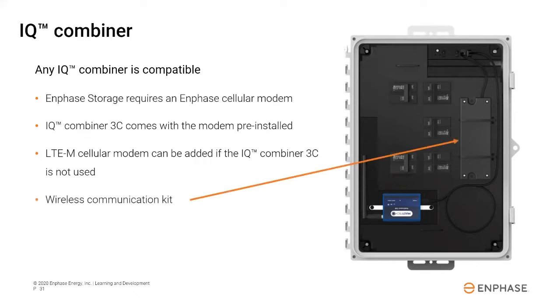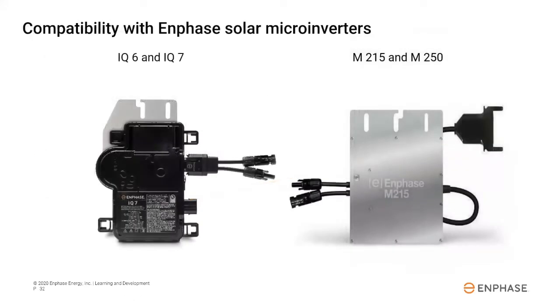And here we have the communication kit. So this must also be installed in the combiner. It's always a separate item. And there's a spot right on the dead front of the combiner box to attach it, and it plugs into the Envoy with a USB cable. Enphase Storage is currently compatible with any solar PV system which uses Enphase IQ series microinverters like the IQ6 and IQ7, as well as M215 and M250 inverters. The M215 came out in 2011, and most of the systems between 2011 and when the IQ6 came out will use one of these two models.